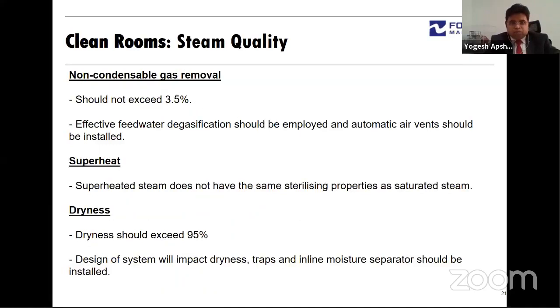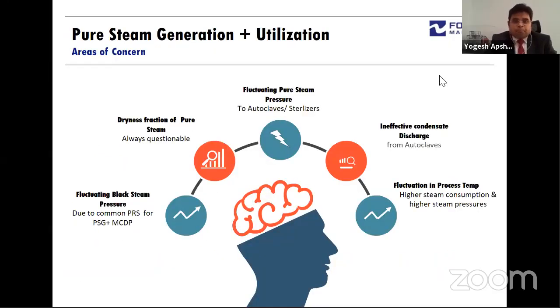Also regarding the clean steam quality, the non-condensable gases and the dissolved oxygen should not go beyond 3.5%. Then effective periodic degasification has to be employed. Then superheat: it should not have any superheat, otherwise it will not give its latent heat as and when it is needed. The dryness fraction should not be below 95%. So these are the typical requirements in the clean room area.